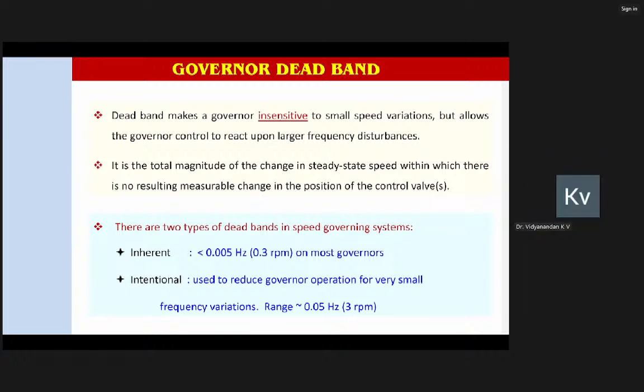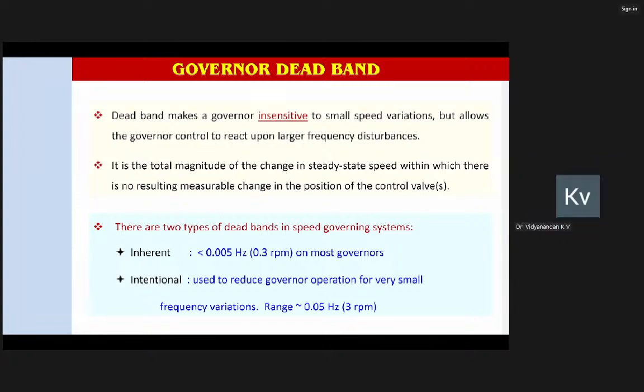Deadband is basically an intentionally set delay, because we know that our design speed is 3000 RPM or 50 Hertz. Whenever the frequency deviates, even say a speed deviation of 0.1 RPM, ideally the governor should respond, but that is actually unnecessary, because even for a minor speed change of say 0.1 RPM or 0.01 RPM, if the governor starts responding, your control valve life will be affected. So in order to reduce those kinds of responses, manufacturers intentionally set a delay. This is what we call the deadband.